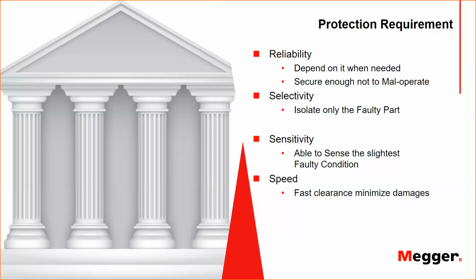Having speed and selectivity, sometimes you have to compromise one for the other when talking about protection systems. But there are some protection principles, like differential protection, that can have both full 100% selectivity and at the same time the shortest, or I would say instantaneous, operation time, both at the same time. So these are the criteria that, when I want to design a protection system, I will always be considering, trying to achieve all of them if possible with the principle I'm using for protection, and with the capabilities and cost, minimizing cost as much as possible, available to me.